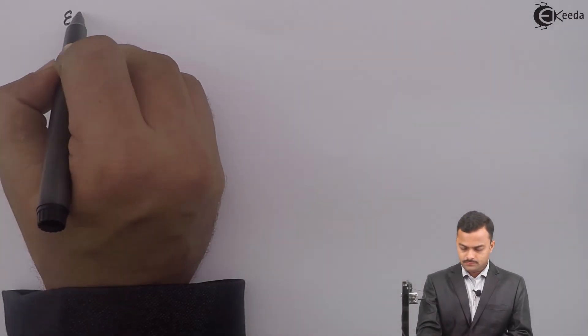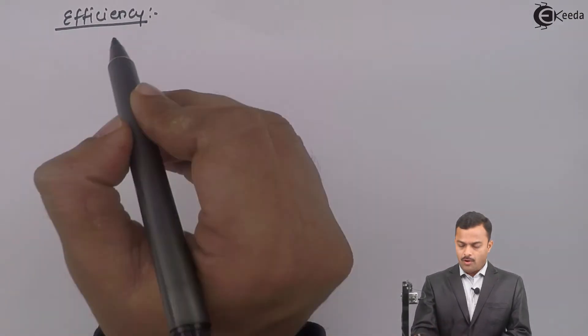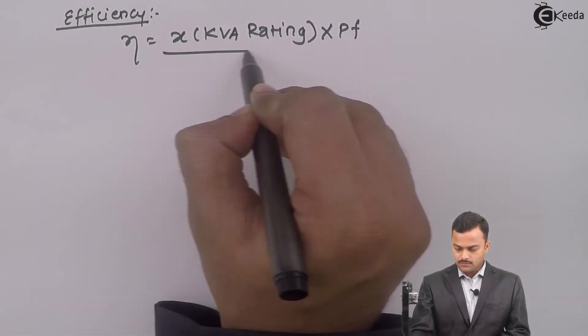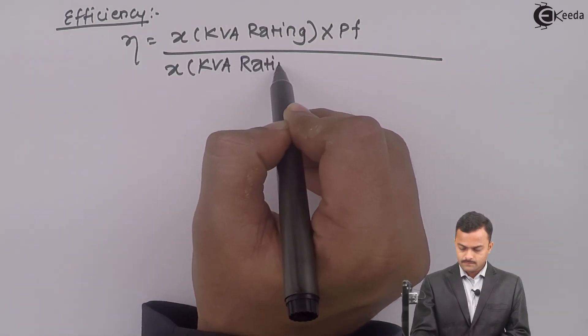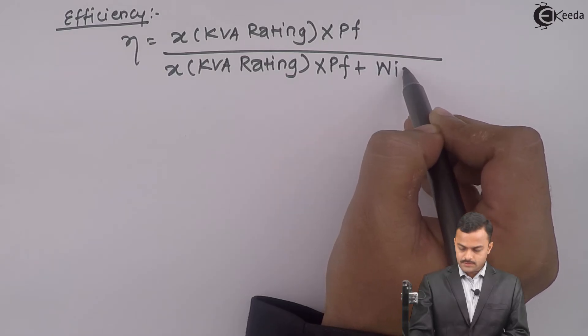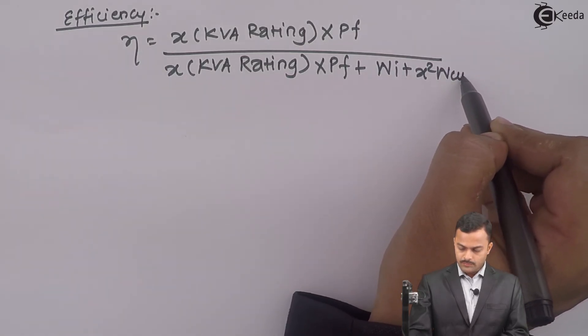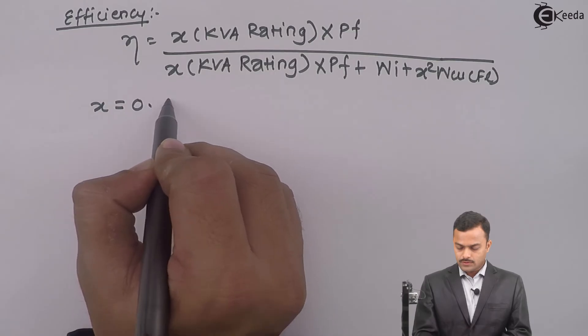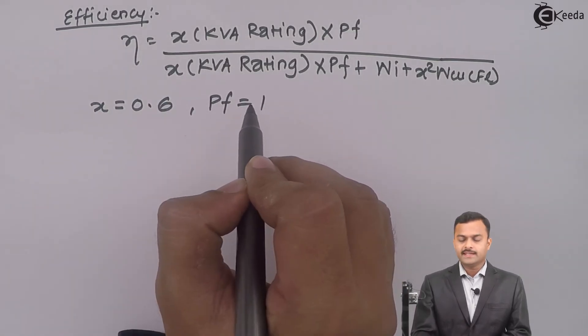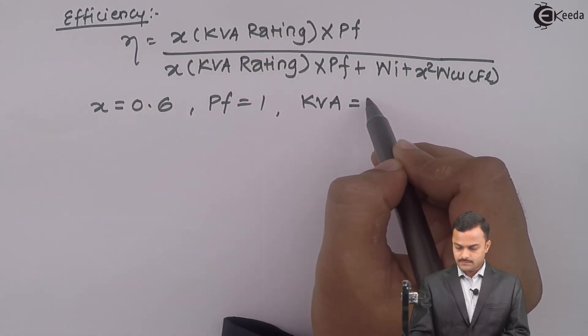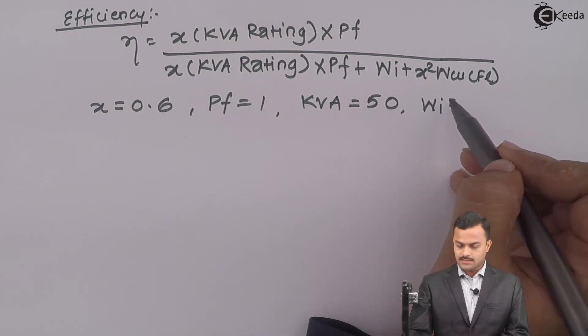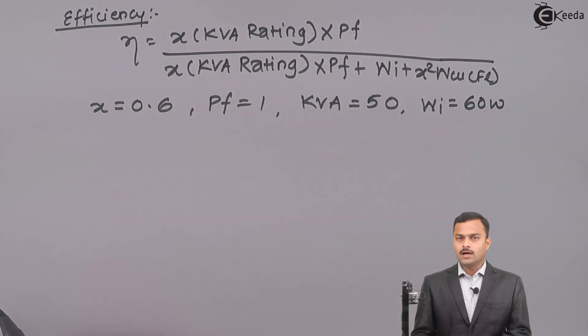Let us go to the second part now. Let us calculate efficiency of a transformer for a given load. The formula for efficiency is X into KVA rating into power factor upon X into KVA rating multiplied by power factor plus iron loss plus X square WCUFL. They are saying calculate for 60% of rated load. Hence X is 0.6, power factor is unity, KVA rating is 50. Whatever power we get for OC test is iron loss, 60 watt.